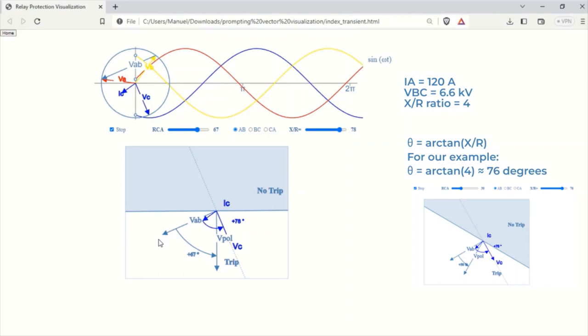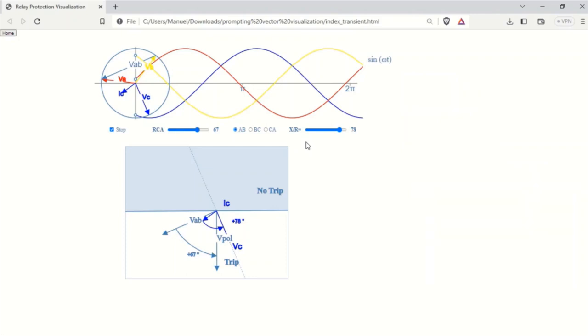Observe the position of the current vector relative to the orthogonal line. If the current vector lies within the trip zone, the relay will send a trip signal to the circuit breaker. If the current vector lies within the no-trip zone, the relay will not take any action.